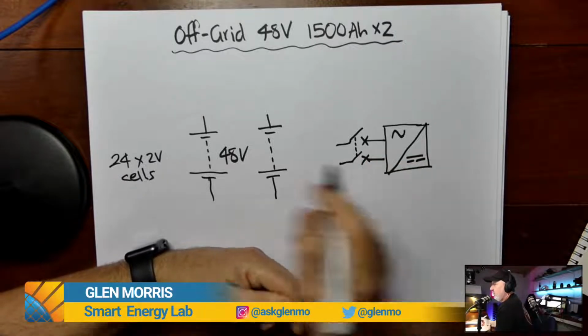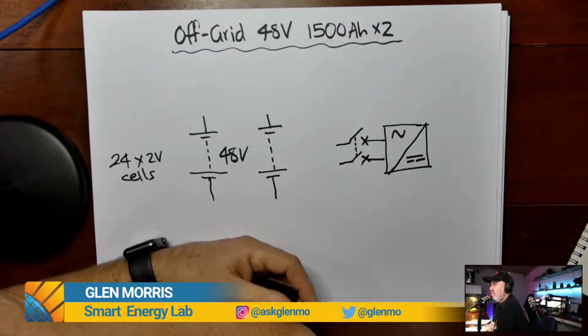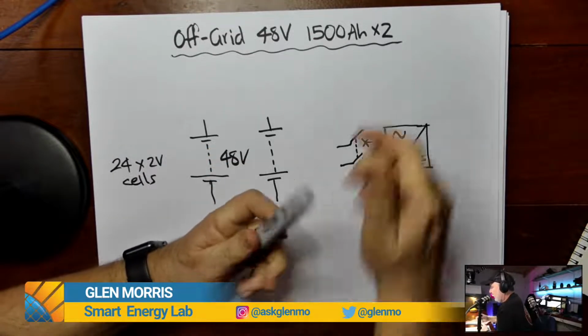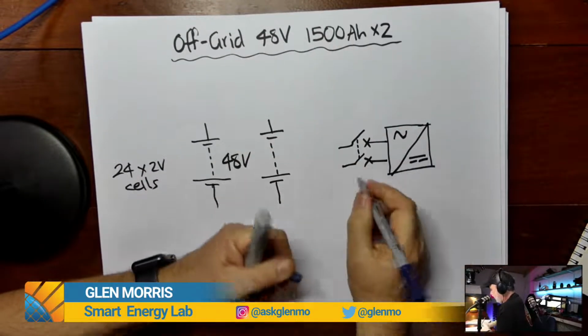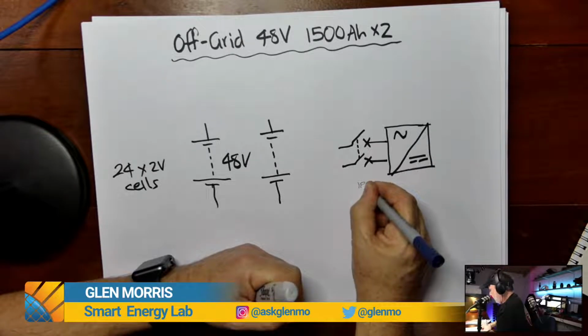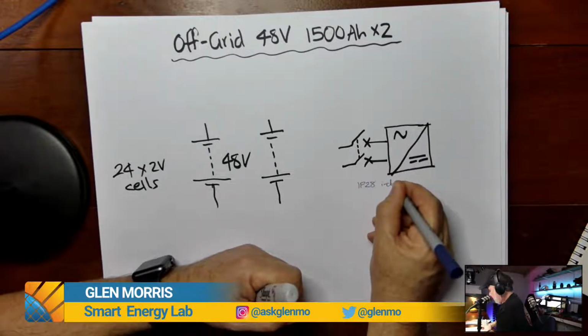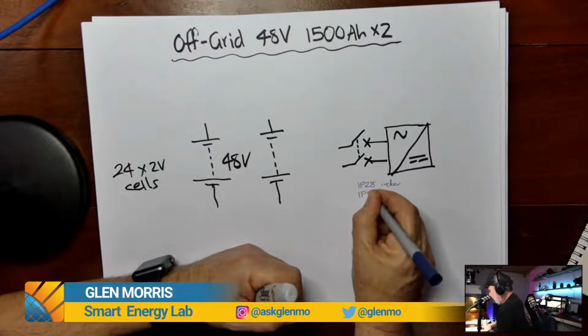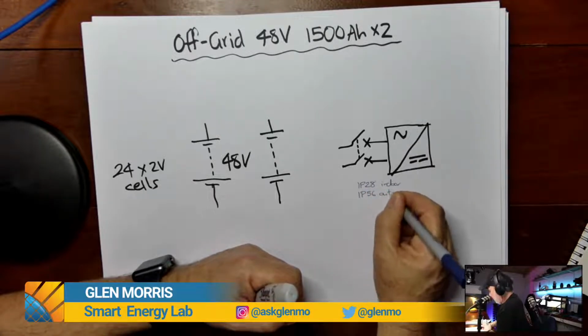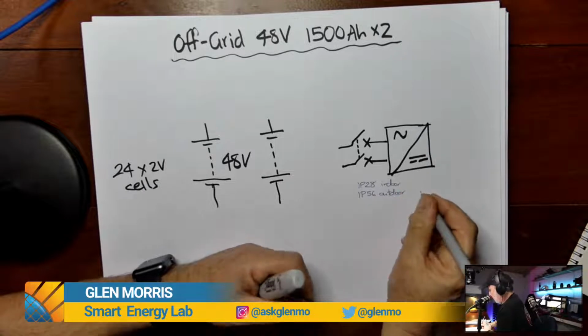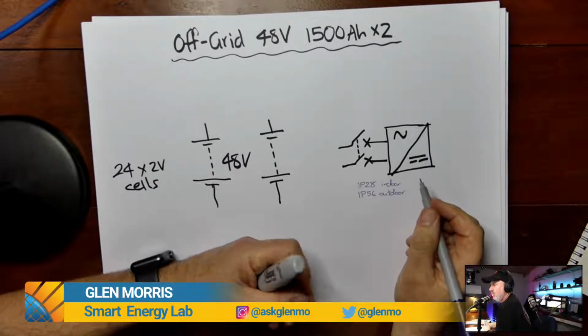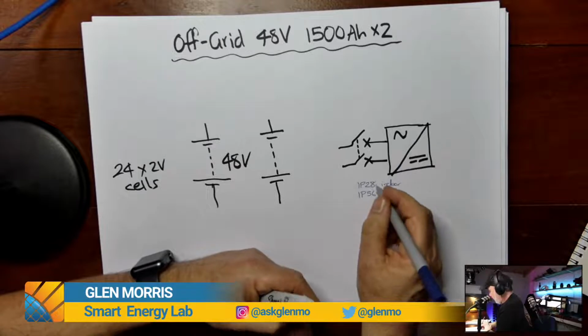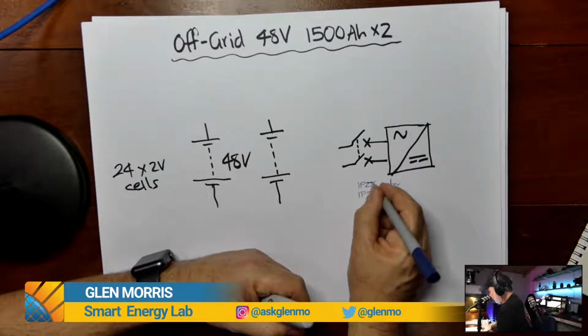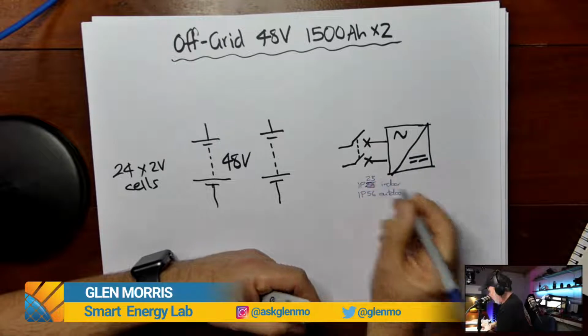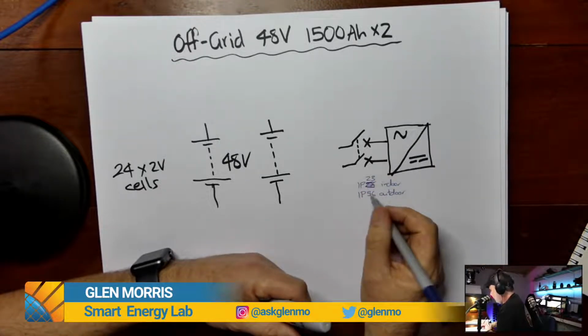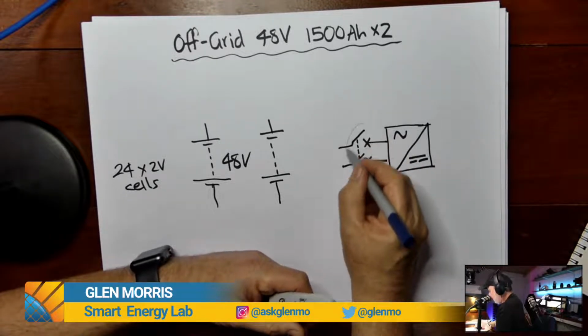Typically, once upon a time, it would have been an HRC fuse switch, but I think that's getting to be problematic these days because the requirement is that if it's indoor, it needs to be IP23, and if it's outdoor, IP56. And because most off-grid inverters generally are indoor products, it's probably going to be IP23. Sorry, I don't know where 28 came from. Don't try and talk and write at the same time. So that's this device here.